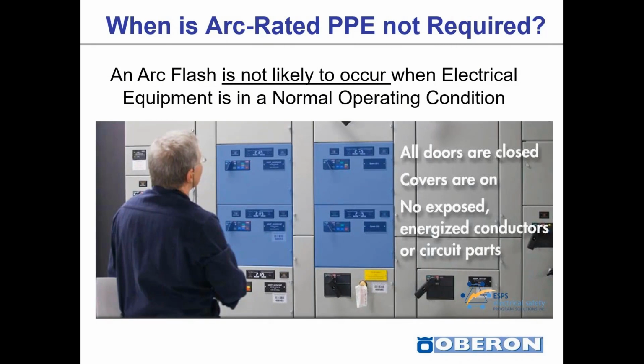When is arc rated PPE not required? It's not likely to occur when we have electrical equipment in a normal operating condition. That's referring to the doors being closed, covers are on, there's no exposed components. The equipment is in a normal operating condition. So there's elements to what is a normal operating condition defined by the standard. And in a normal operating condition, we don't anticipate an arc flash because the likelihood of occurrence is so low that we don't require a worker to wear arc flash PPE.